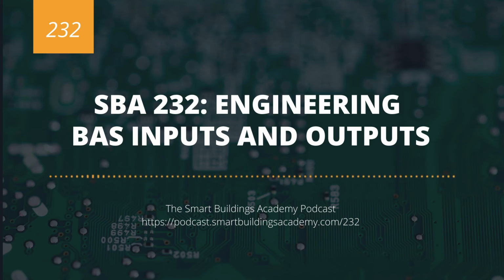So I'm a little confused now. Is this single stage and two stage water source heat pumps? Are these systems that are going to be having building automation controllers on them, or are they going to be having BACnet interfaces? Which one is it going to be? What am I going to be doing with these systems? And therein lies one of the things that can kind of get you hosed up, especially when you're dealing with schools or maybe potentially low cost projects that have factory packaged controls, or maybe they have the option for factory packaged controls, and we're just doing an interface. So we really got to get clear.